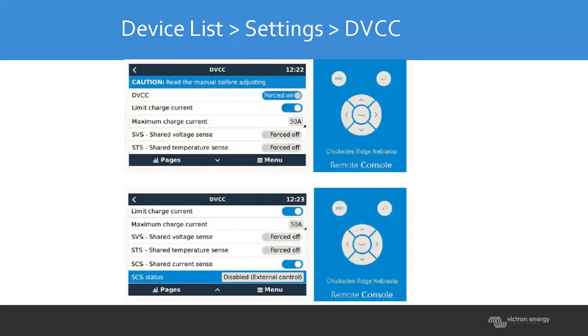This is the only setting you really have to mess with, the maximum charge current. So getting back to the 50 amps that my generator would provide, I can provide 50 amps DC. So you set that. The shared voltage sense, or SVS, is forced off. The shared temperature sense is forced off.